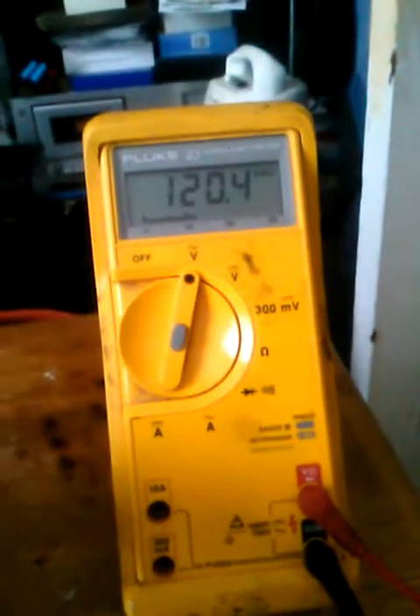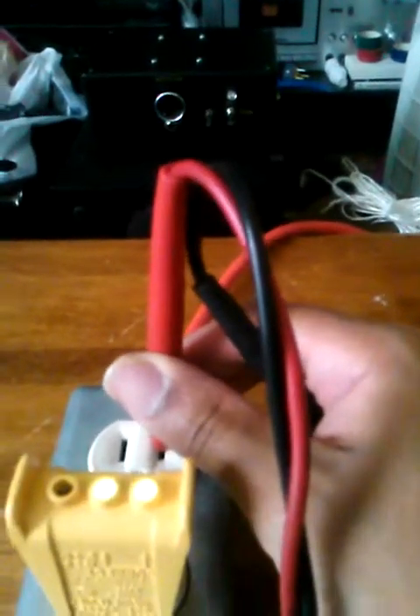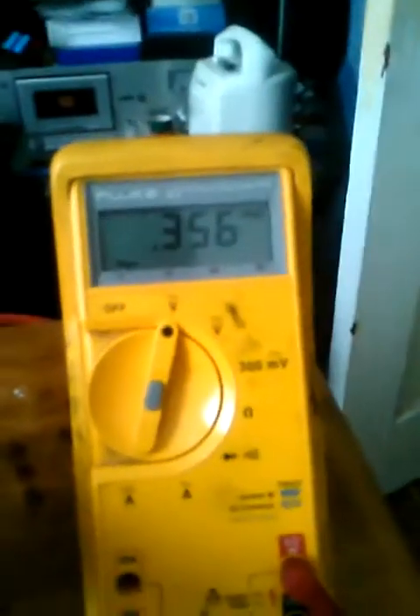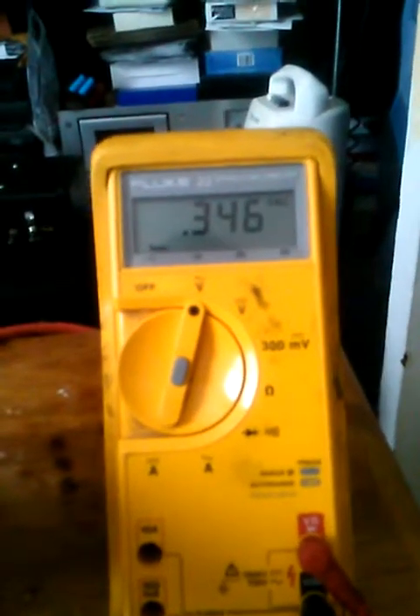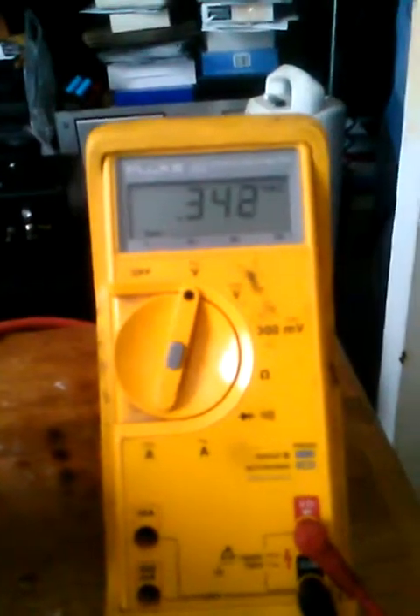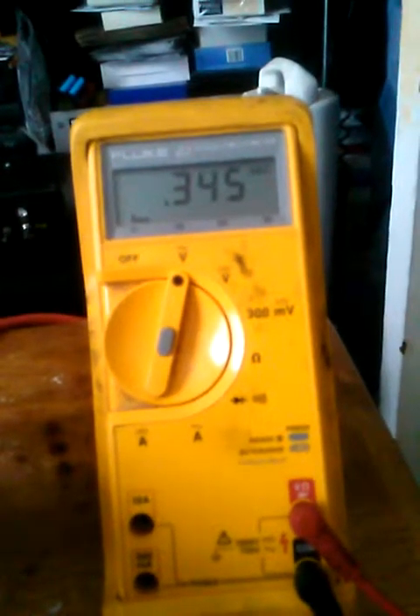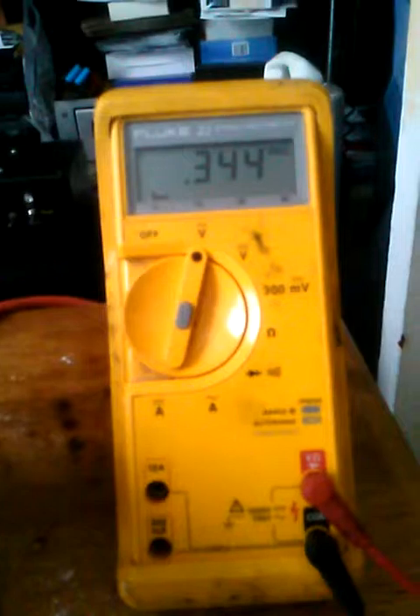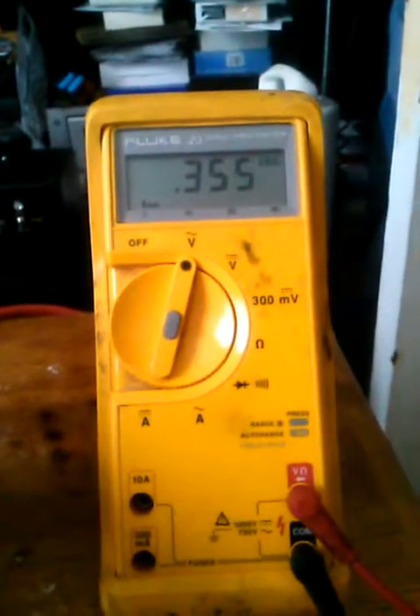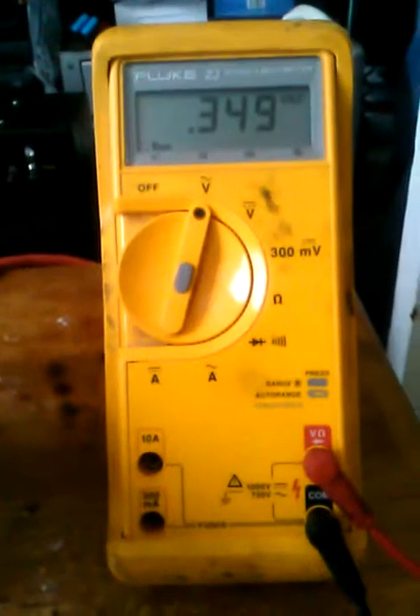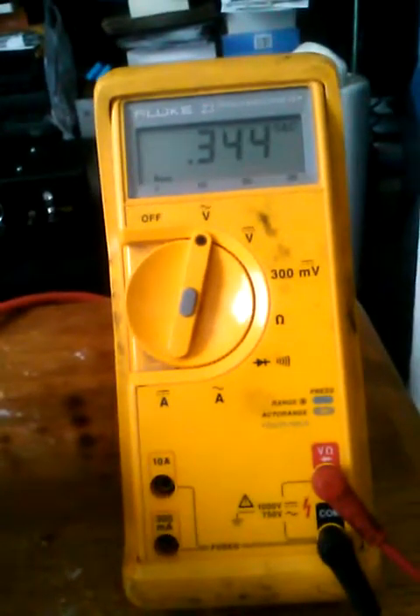Now, to test for polarity again, to make sure that the electrical outlet is wired properly, you would simply take the same probe, put it into the neutral side of the outlet, and then touch the box again, or the screw here, or this ground prong here. It should read less than 1, which tells me that this outlet is properly grounded and the polarity is correct on the receptacle. So that should be 0, or 0 point whatever negative value it is.